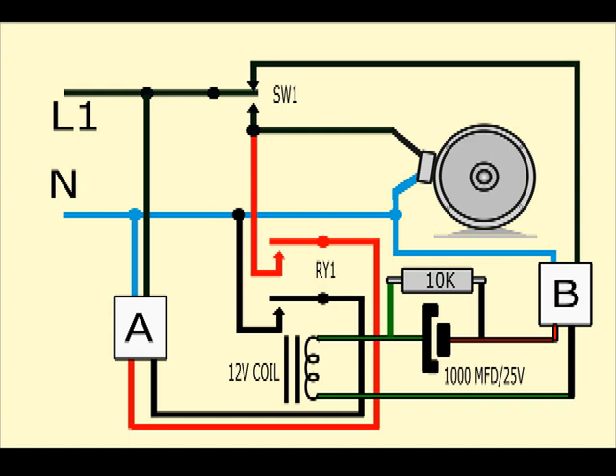You must experiment with several values of the resistor and capacitor while the motor is disconnected to make sure the braking time is just right. The relay should only be energized for one second.